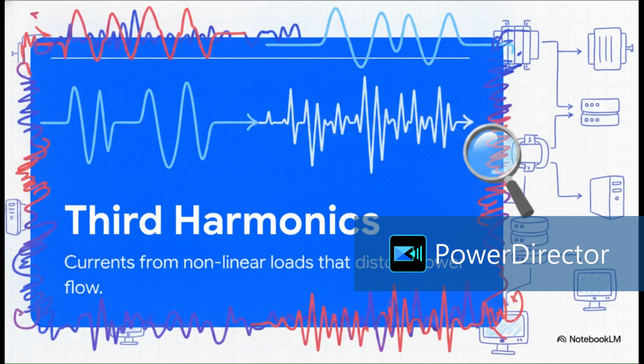The true culprit behind this whole mystery is a phenomenon called third harmonics. When nonlinear loads operate on an electrical system, they act as sources that generate and produce these third harmonic currents. So this isn't your standard clean power flow anymore, this is a severe distortion of the normal current.